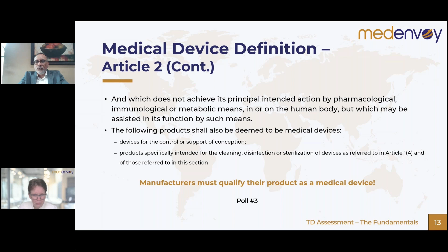Moving on to the next fundamental, which is classification of your device. When you are classifying your device, your technical documentation should explain the process that you have followed for classification. Don't just code it as class 2A against rule 5. That's not adequate. We need to see these are the rules that we have followed. We did not apply this because it's an active device, so we only applied the active devices rules. We use this because it's a system, it's not only software.